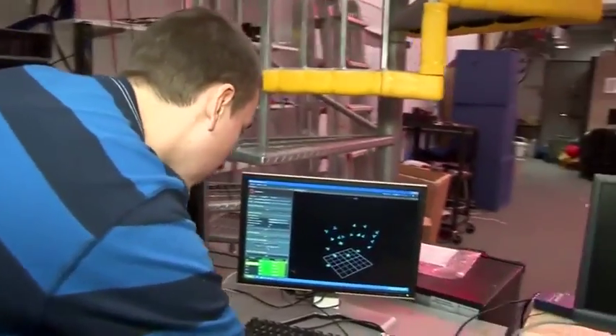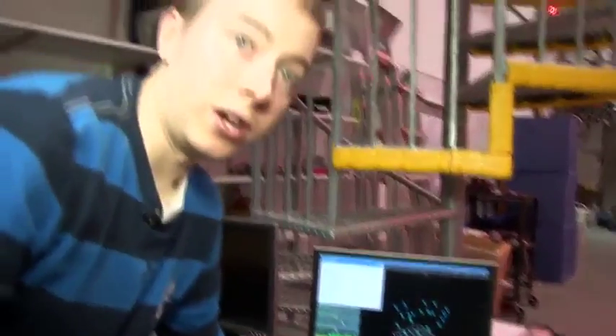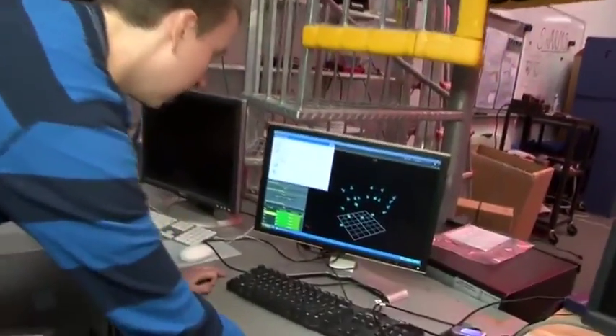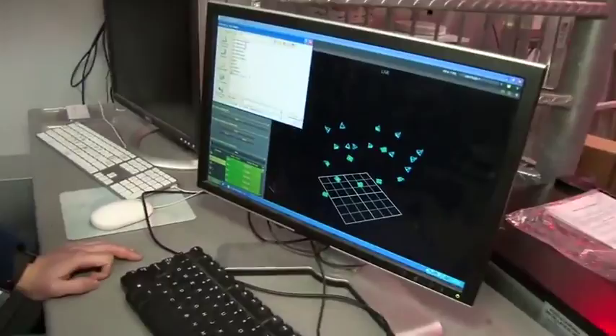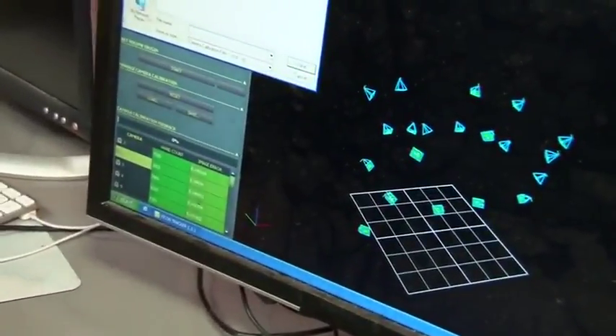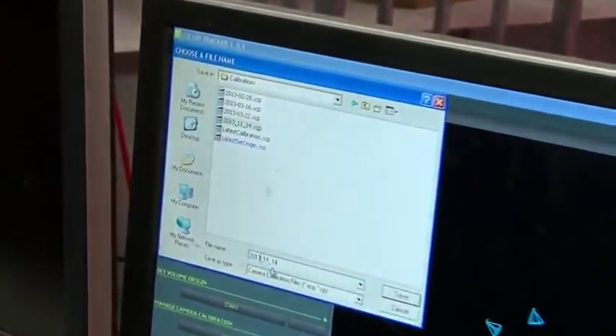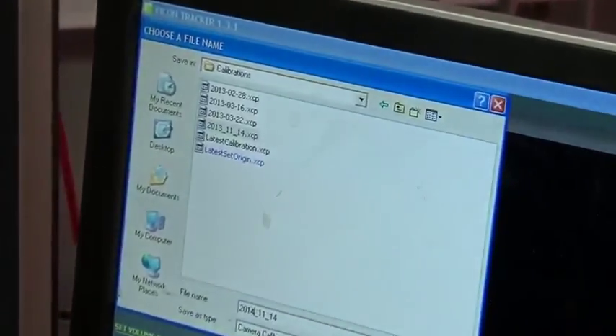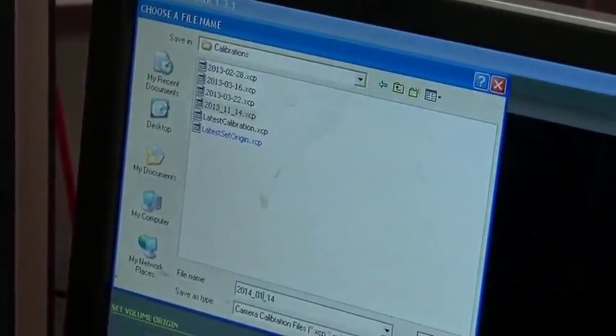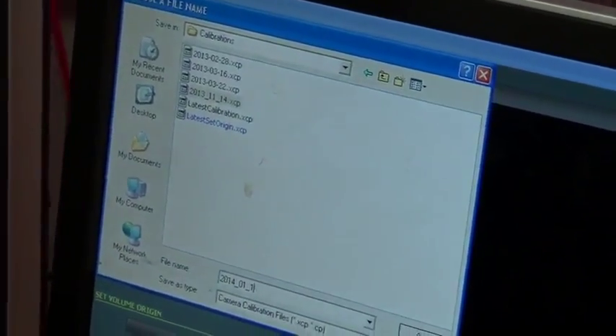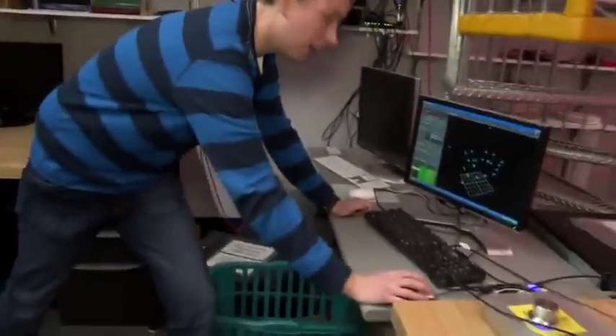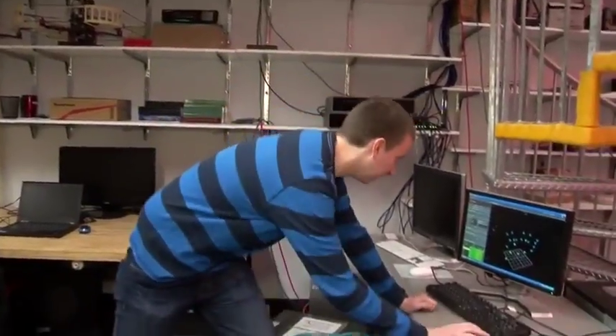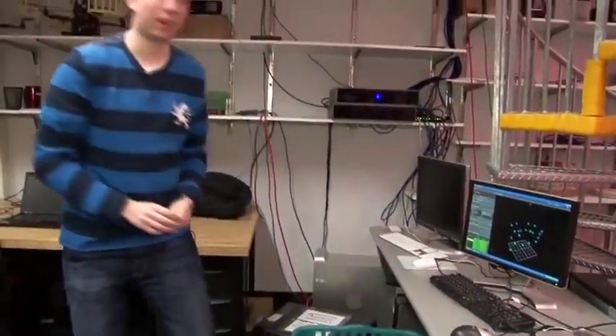Finally we need to save this calibration, and we can do this into the calibrations folder and label that correctly with the date. And now this calibration has been saved and ready to use. And that's calibration.